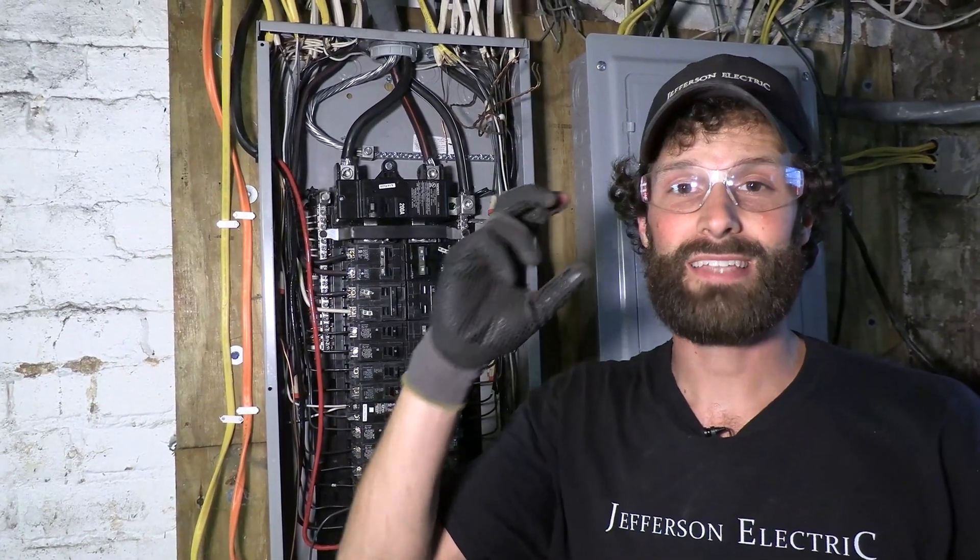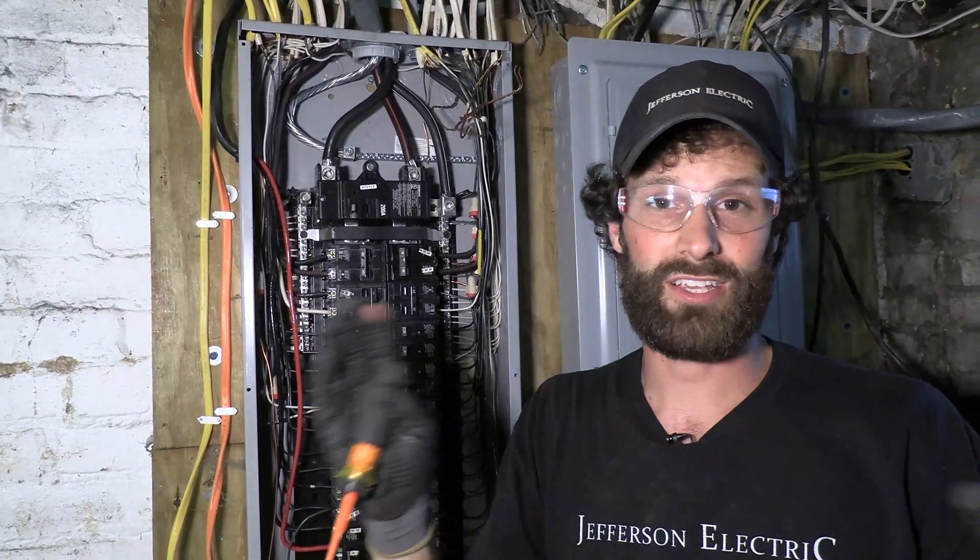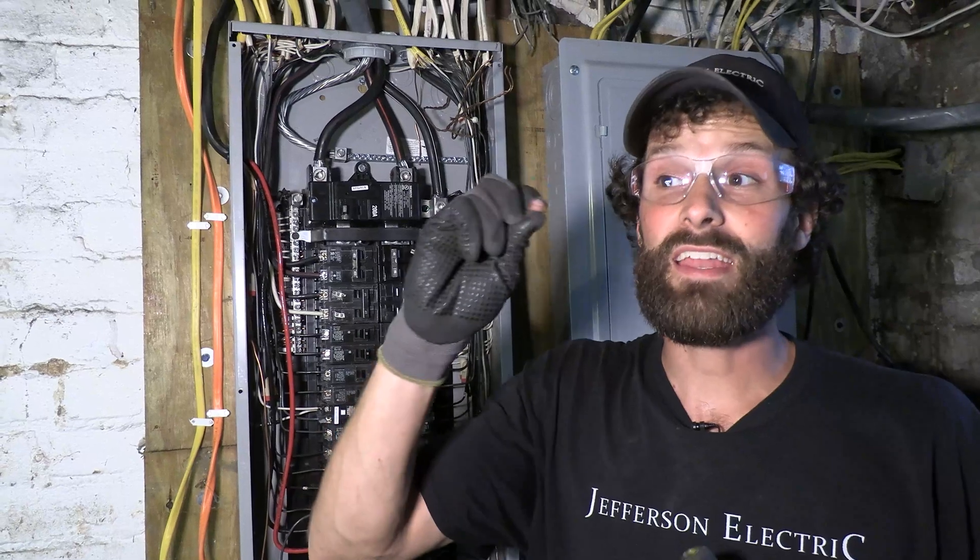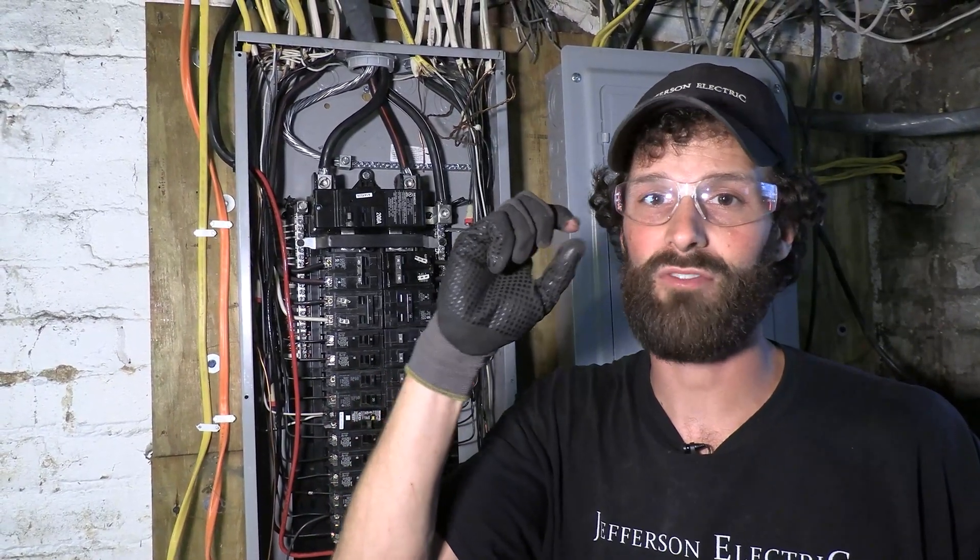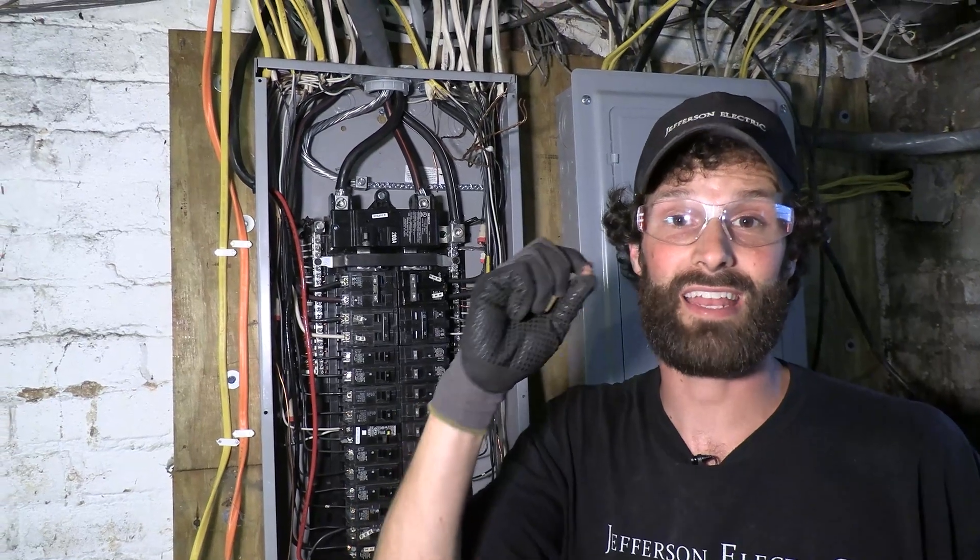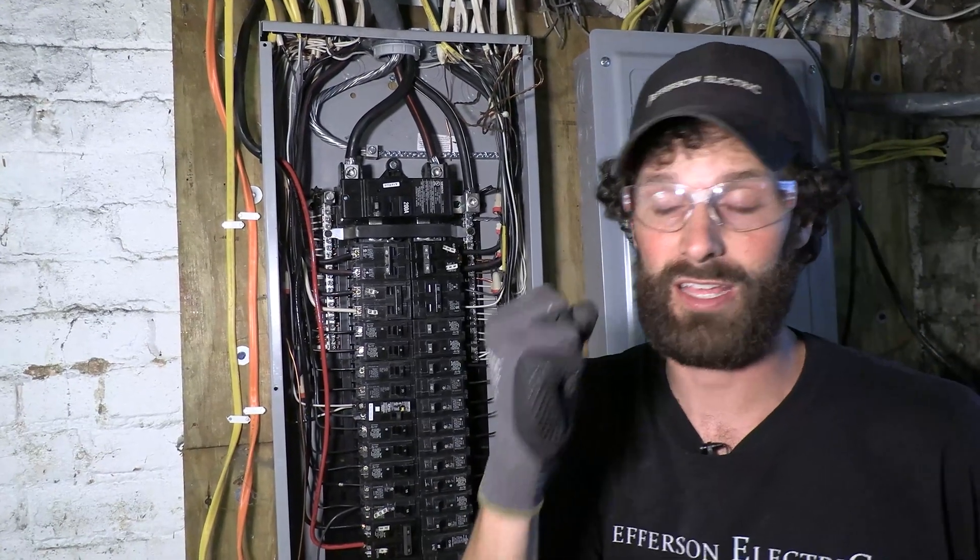Also never put two differently sized conductors together. If you have a larger 10 gauge conductor with a smaller 14 gauge conductor, works just like shotgun shells, then that 10 gauge conductor will get clamped and pinched down but that 14 gauge conductor will still slide in and out because it has a substantially smaller diameter and you won't have the proper compression on it.